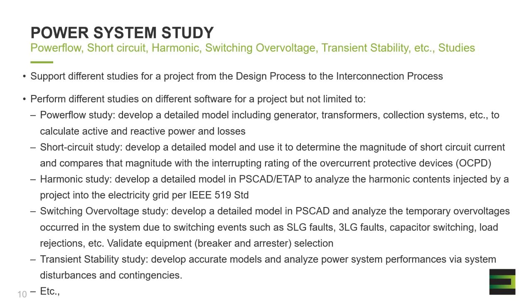There are a few other transient studies that include switching overvoltage. This is mainly performed in PSCAD software, which captures the transient behavior of the different models and inverters to ensure that the project and the equipment within the BOP will not be damaged in case of a lightning strike or a switching surge that may happen during different faults within the project or outside the project. And last but not least, transient stability study. This is performed to evaluate the transient behavior of the project during different contingencies and grid conditions.